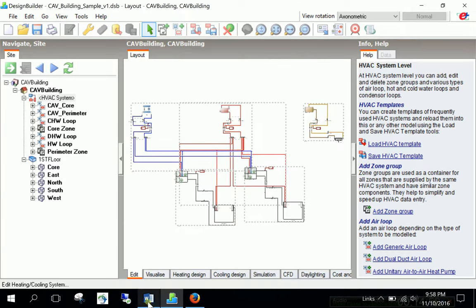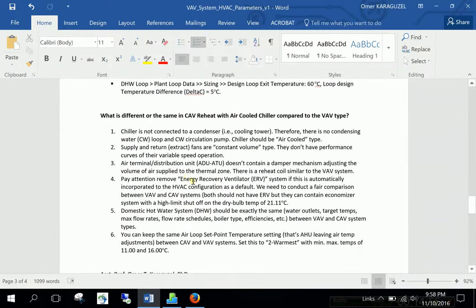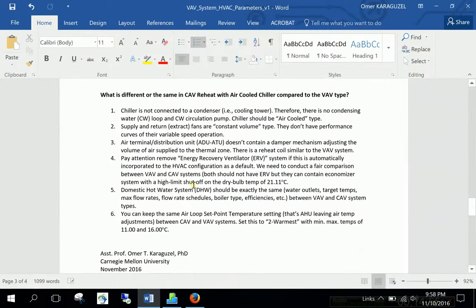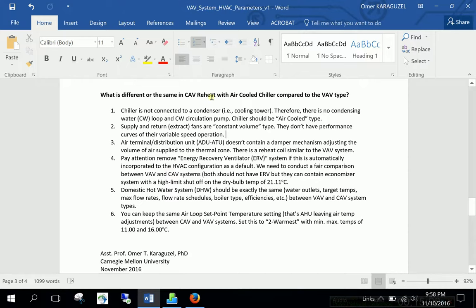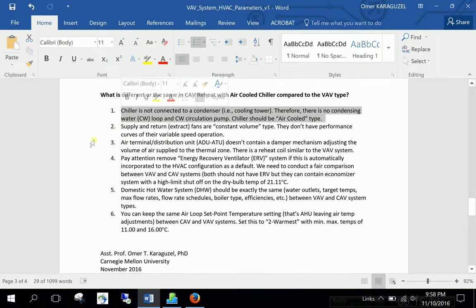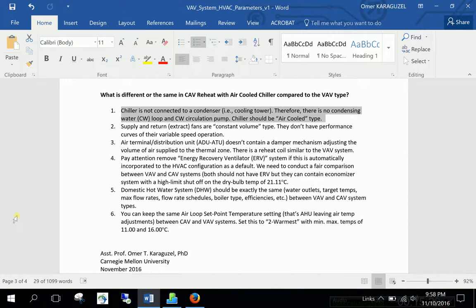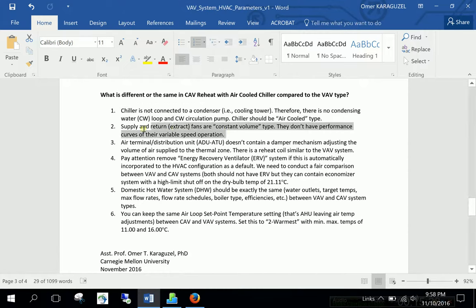Now I will open up this word file. Here it is. And in this word file, we have a list of what is different or the same in CAV reheat with air cooled chiller compared to the VAV type. So there are different bullet points. The first one is chiller. In the CAV is not connected to a condenser or a cooling tower. So there is no condensing water loop. And no condenser circulation pump. Because the chiller is air cooled at the CAV.